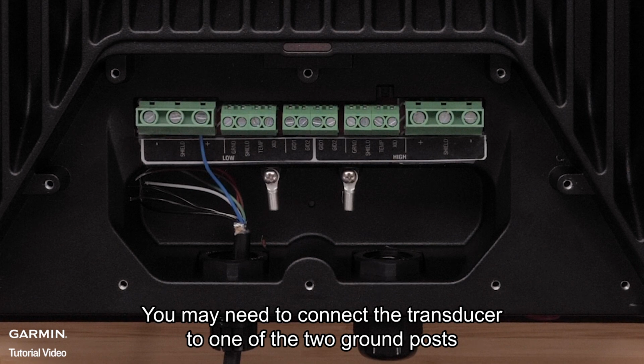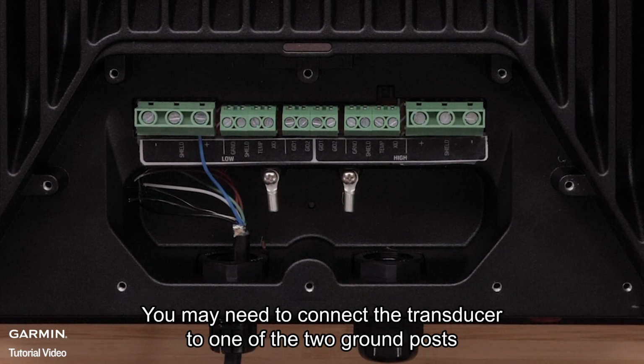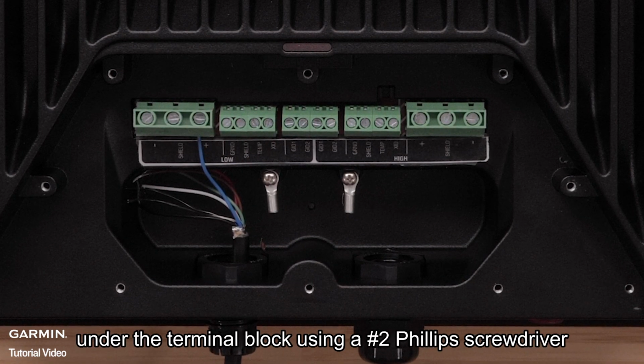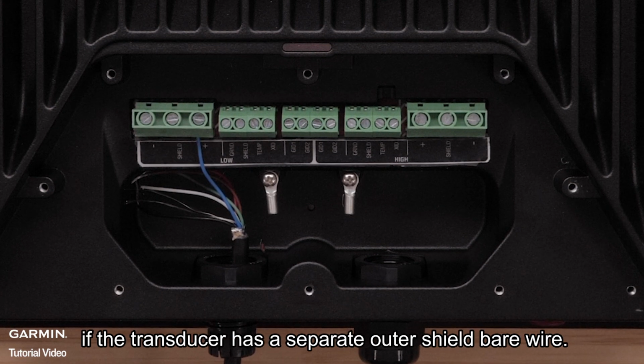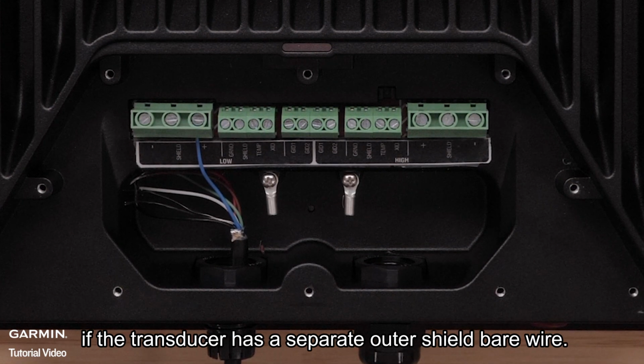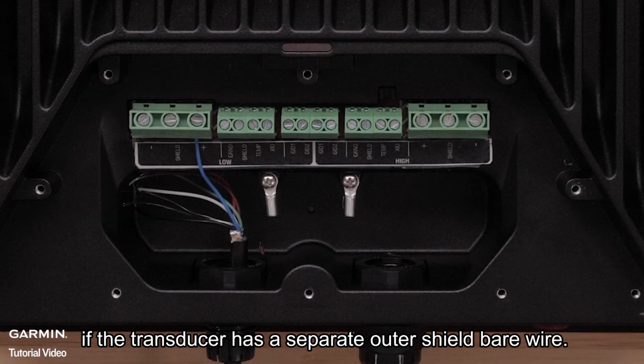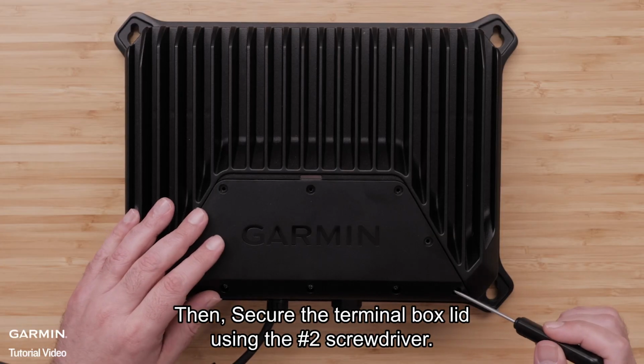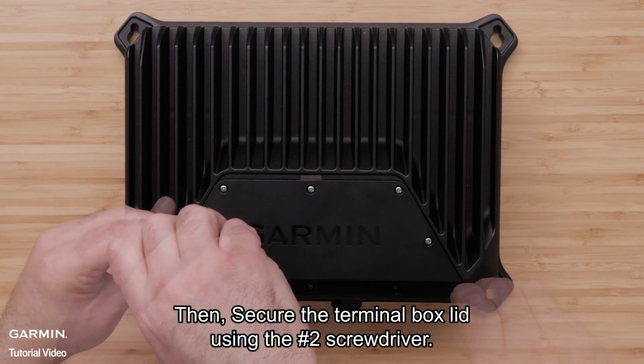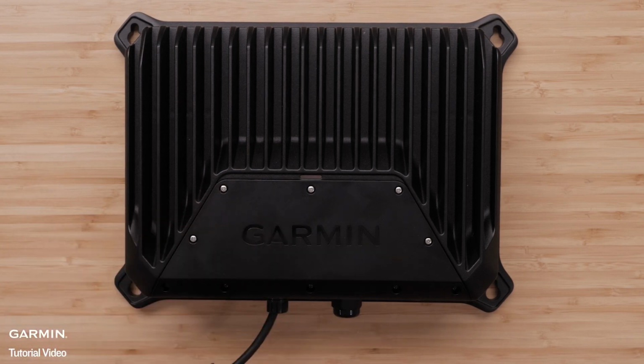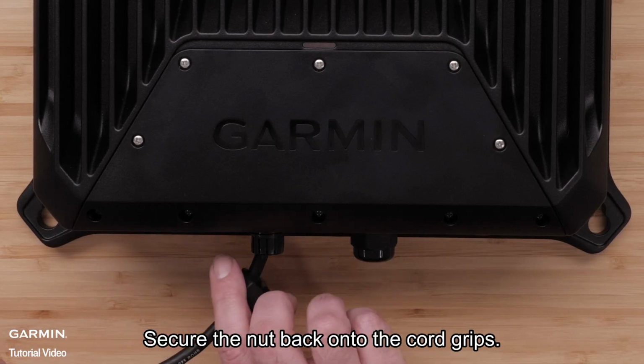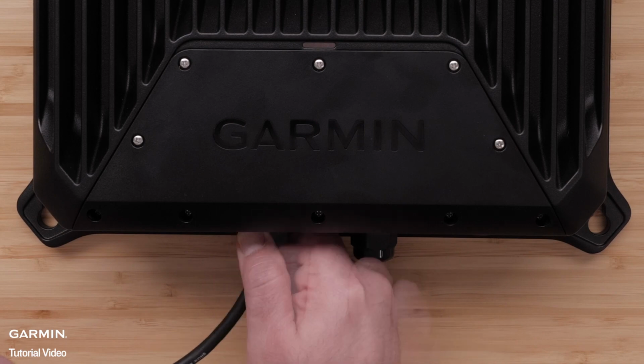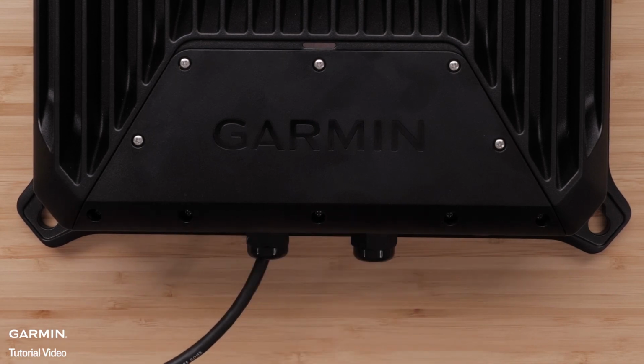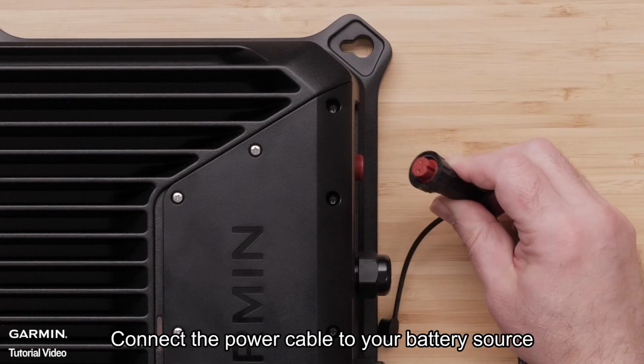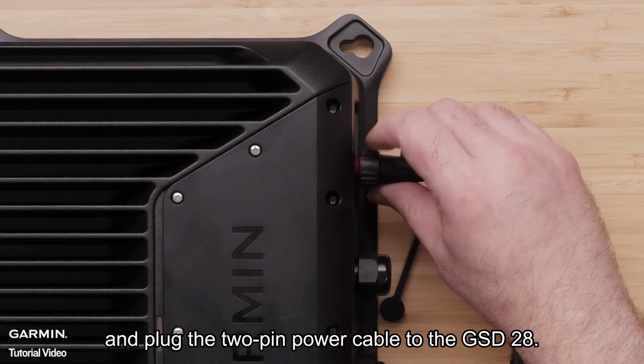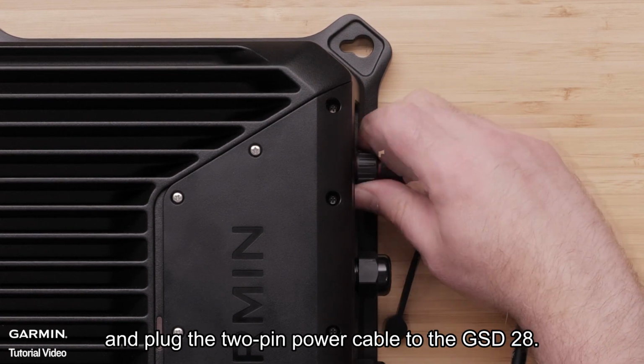You may need to connect the transducer to one of the 2 ground posts under the terminal block using a number 2 Phillips screwdriver if the transducer has a separate outer shield bare wire. Then secure the terminal box lid using the number 2 screwdriver. Secure the nut back onto the cord grips. Connect the power cable to your battery source and plug the 2-pin power cable to the GSD 28.